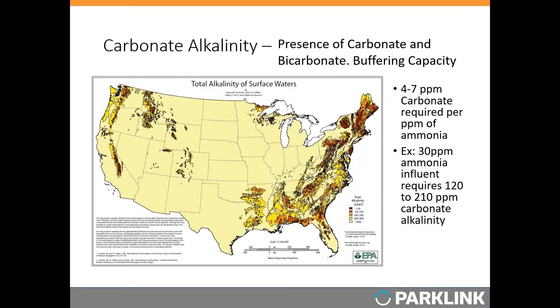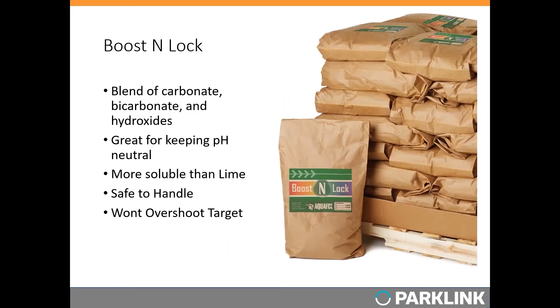Not all plants in low-alkalinity areas will end up with alkalinity deficiency because suspended solids added to wastewater can add alkalinity. If you do have low alkalinity, common additives include soda ash or lime — though lime is not very soluble, making it difficult to use, and at high rates it commonly causes scaling issues in pumps and lines that can lead to complete blockages. If you have low alkalinity or see pH swings from high acid to low acid or high basic, that may indicate low alkalinity.